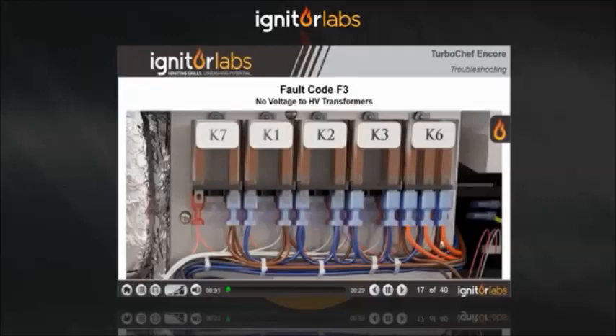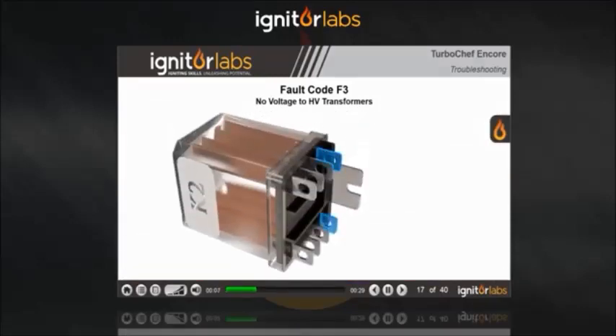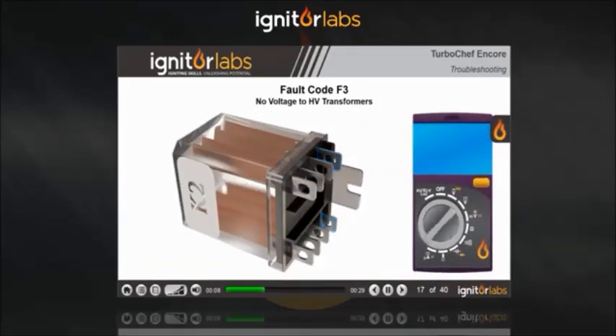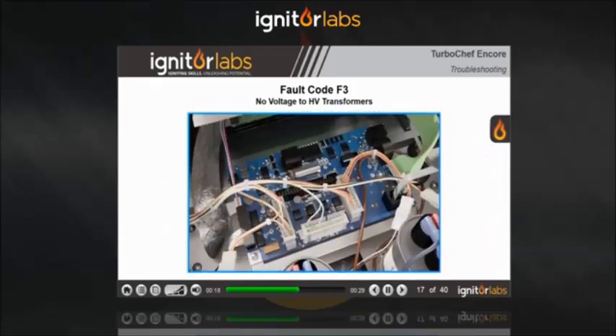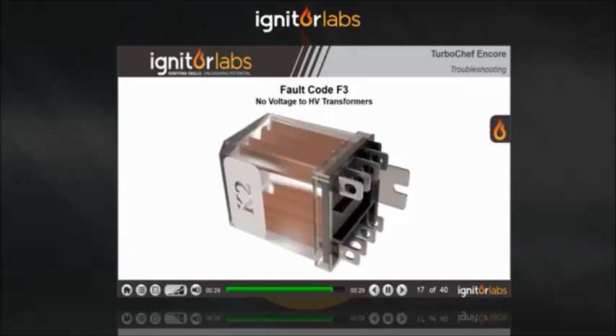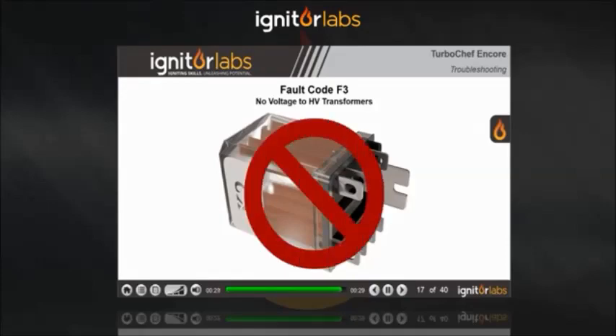If there's no voltage present at the high voltage transformer, check the K2 anode relay. First check for coil voltage from the main control board. When it's calling for microwaves, you should see 24 volts DC at the coil. If there's no voltage, check the wiring back to the main control board. No output means a malfunctioning board. With the correct coil voltage, the relay should actuate. If it doesn't, you have a faulty relay.